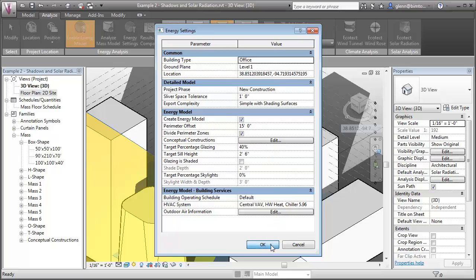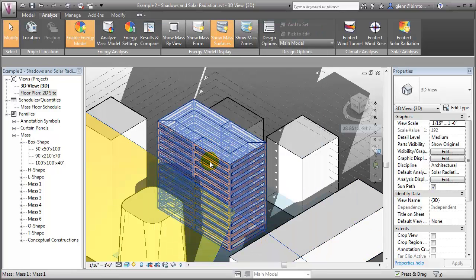But surfaces that receive a relatively high level of solar radiation, typically those on the south side of the building, need to be considered especially carefully. On one hand, we'd like to maximize the percentage of glazing area on these surfaces to capture more solar radiation to assist with passive heating during the coolest months. But on the other hand, too much glazing on these surfaces can result in capturing too much heat during the summer and increasing our air conditioning loads.